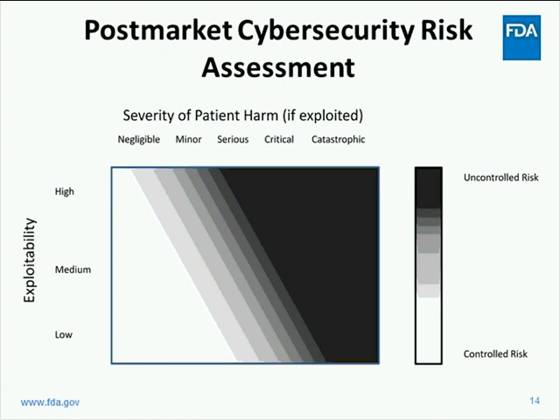The risk matrix is a visual representation of the proposed assessment, with exploitability on the y-axis and severity of patient harm if exploited on the x-axis. Together, the assessment yields risk of patient harm. The manufacturer must assess whether the risk of patient harm is controlled or uncontrolled.